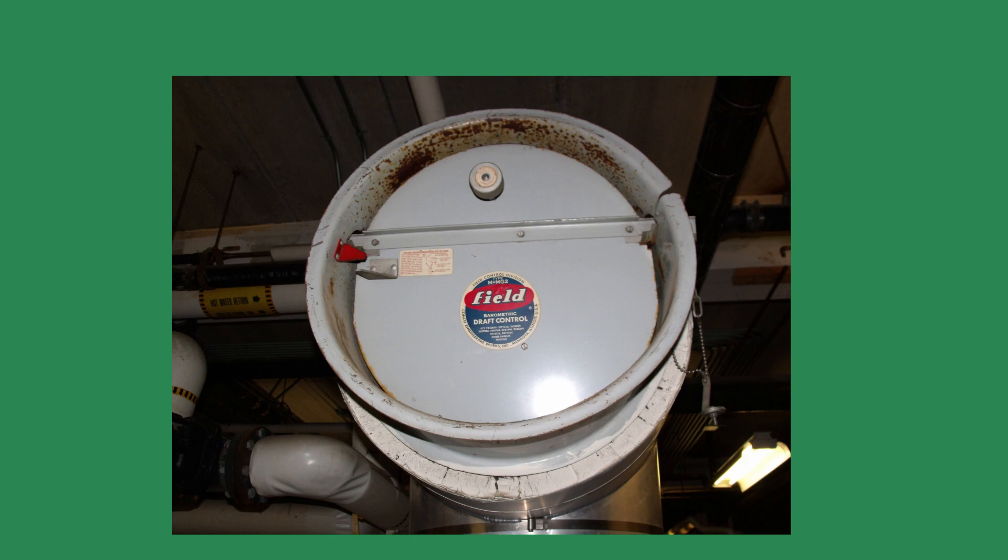Barometric dampers are only installed on boilers with negative venting. Boilers with pressurized vents would spill flue gases from the barometric dampers into the room.